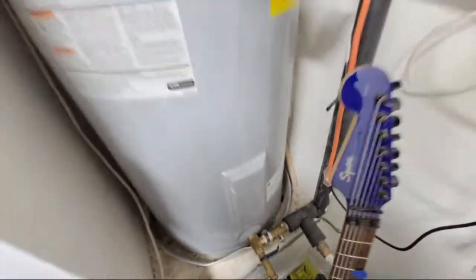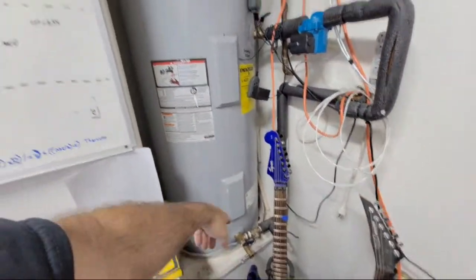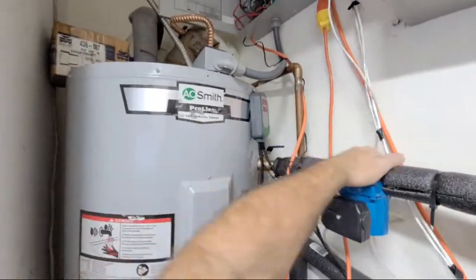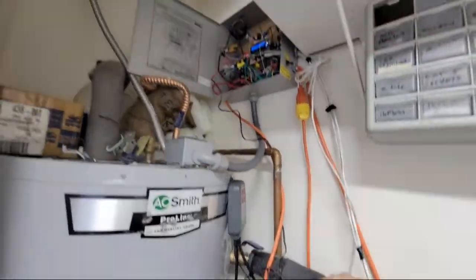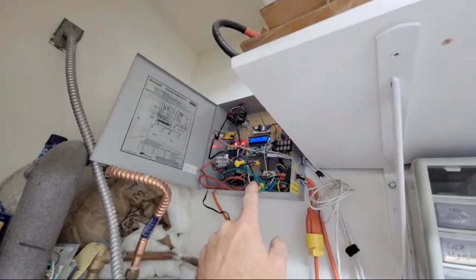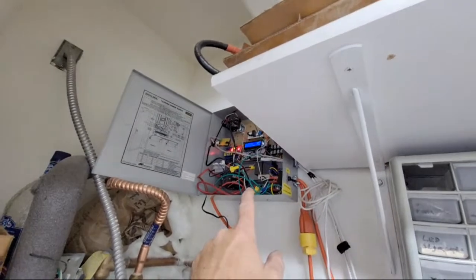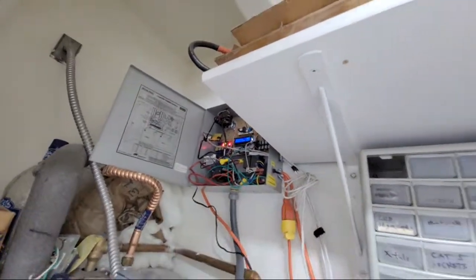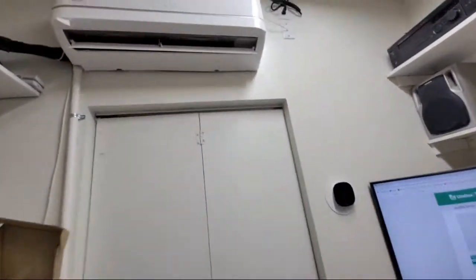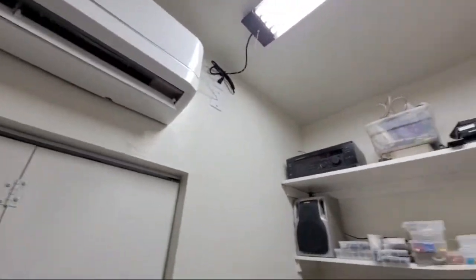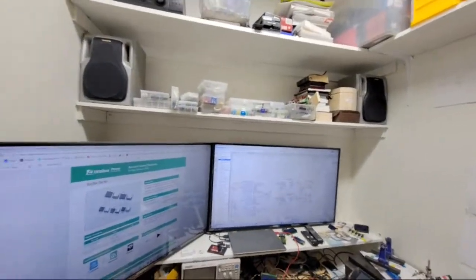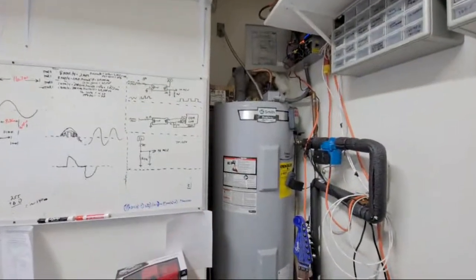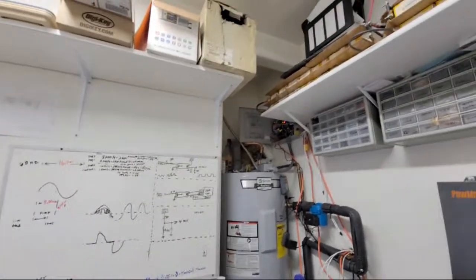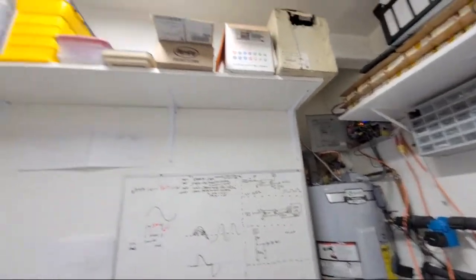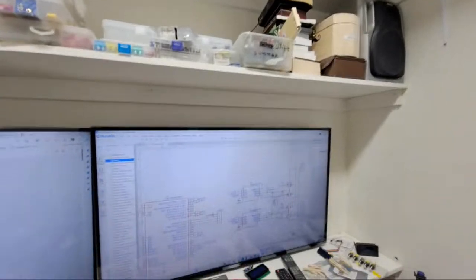It's pretty hot, but it's always cooler at the bottom of the tank. It's coming back at 136, freaking hot, and it's killing my performance, my cooling a little bit. My suction line's up to 67, and my liquid line's 122. This is when I want to use this room. Again, for those that don't know, the compressor out there is cooling this room while heating the water at the same time. I did add a little bit of outdoor coil, but not a whole lot, just to keep the pressure from going too high.